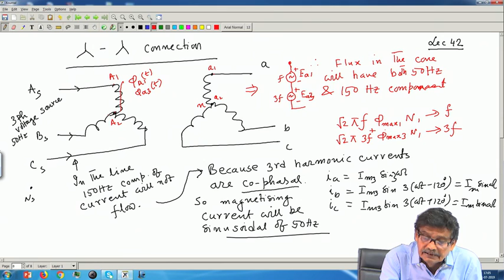And this induced voltage will be also here in the secondaries, because the same flux links both primary and secondary. Therefore, across the phases of both primary and secondary, as if there will be two sources of EMF. Between A and this small n, there will be one source E A 1 and another source E A 3, of course of different frequency, f and 3 f. Two sources of EMF will be existing between A 1 and A 2, and similarly for B phase and C phase. Therefore, across the phases both in primary and secondary coils, the induced voltage will have a 50 hertz component as well as 150 hertz component. Okay, and that is what I am telling is not desirable.